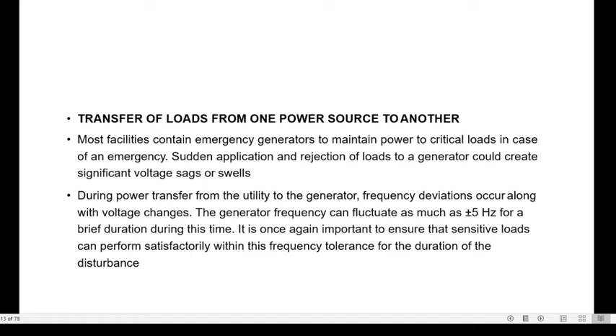During power transfer from the utility to the generator, frequency deviation occurs along with the voltage changes. The generator frequency can fluctuate as much as plus minus 5 Hz for a brief duration during the switching of the load from utility to the generator. It is once again important to ensure that sensitive load can perform satisfactorily within this frequency tolerance for the duration of the disturbance. Otherwise, it will go under under-frequency operation, giving more frequent tripping.